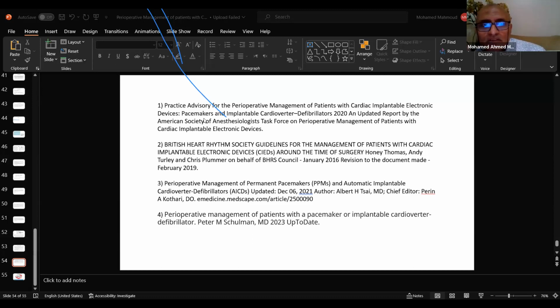And usually when we put the magnet on the pacemaker, it will convert the mode of pacing from synchronous to asynchronous. And the rate in asynchronous mode depends on the manufacturer settings and the settings done to the device during insertion by the CIED team. And sometimes even the rate of asynchronous mode is affected by the battery life. If the battery is weak, the rate of asynchronous mode is lower than the preset rate of pacing.